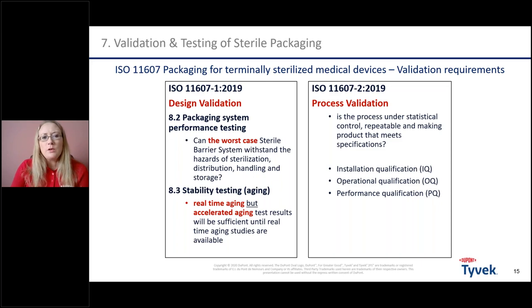But not only process - you should also validate your design, outlined in part one of the standard. Packaging system performance testing has to be performed, like distribution simulation on the worst case sterile barrier system, because you need to show that your selected packaging design and materials can withstand all the challenges throughout the packaging life cycle until the point of use.